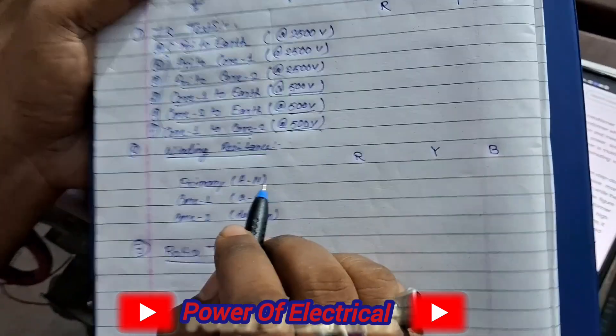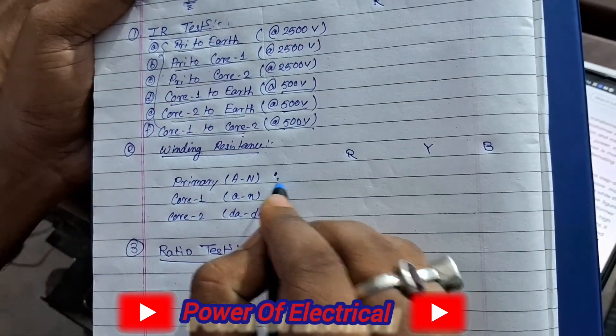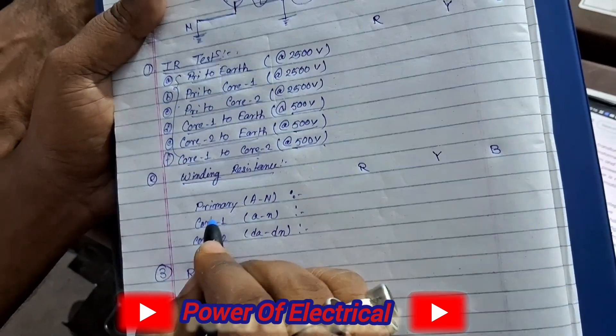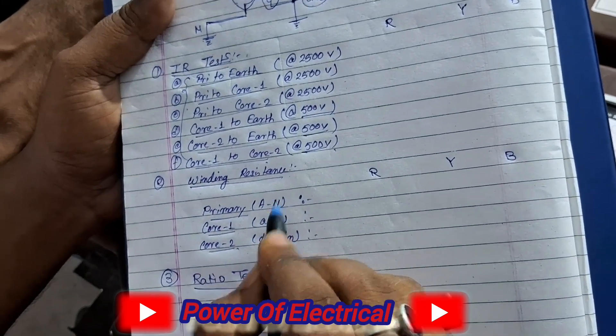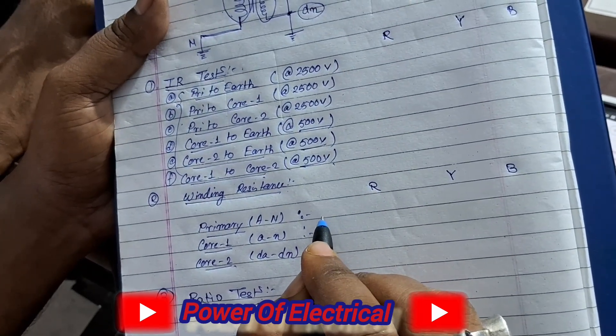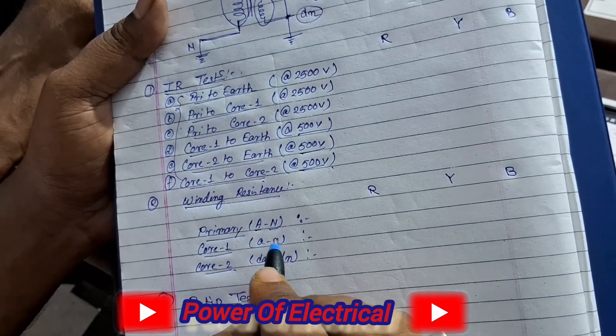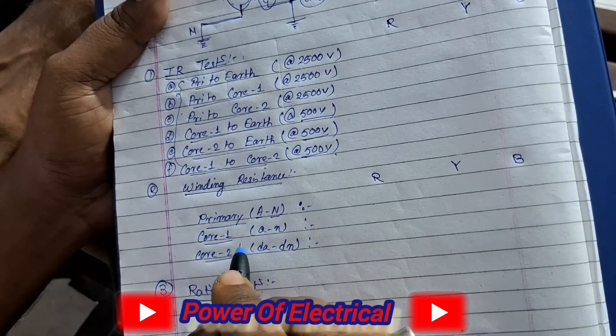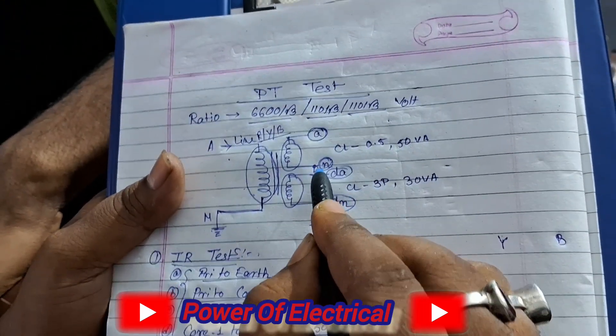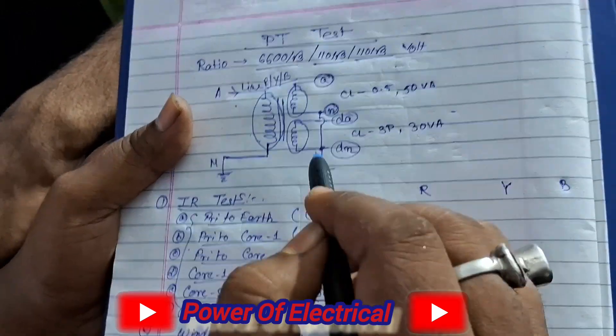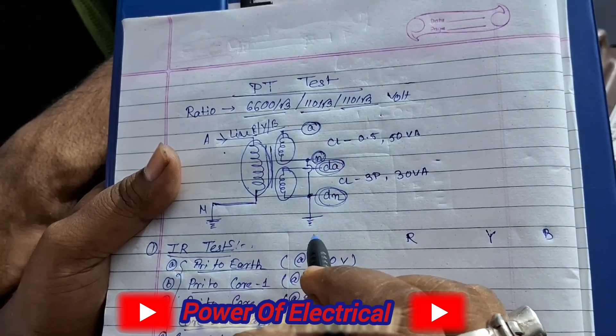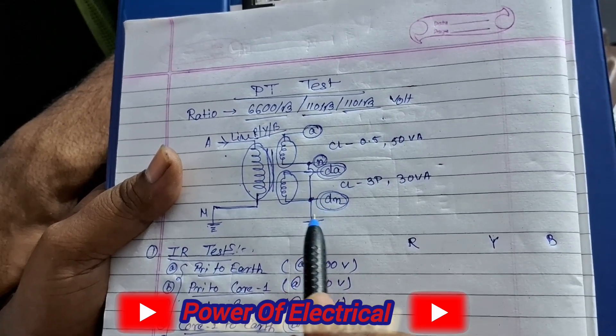For the winding resistance test, we simply use a multimeter to measure the winding resistance of the PT. In the PT there are three cores: primary, secondary core one, and secondary core two. We take three different resistance values. For primary resistance, we connect the multimeter probes to terminals A and N to get the primary resistance. For core one, we connect the multimeter probes to small A and small N terminals. For core two, we connect the probes to DA and DN terminals.